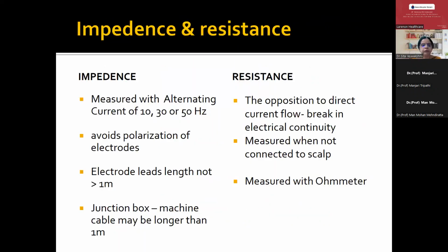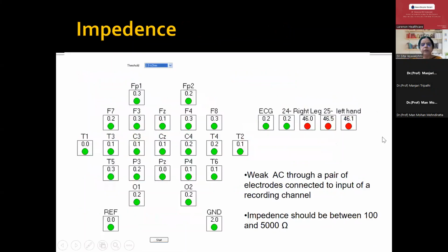And after this, we should know what impedance and resistance of the machine are. Actually, both may sound synonymous, but impedance is measured using alternating current, whereas resistance is the opposition to direct current flow, which usually gives the break in the electrical continuity. And normally we measure impedance once we connect all the electrodes. And how do you really check this? A machine automatically gives you the impedance.